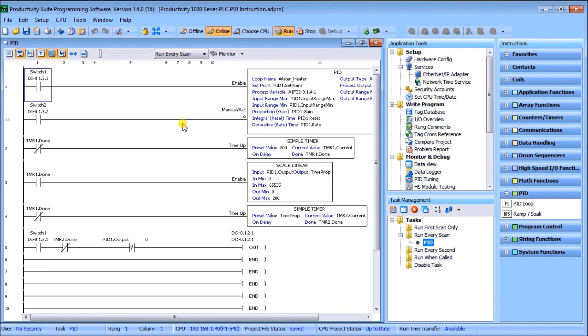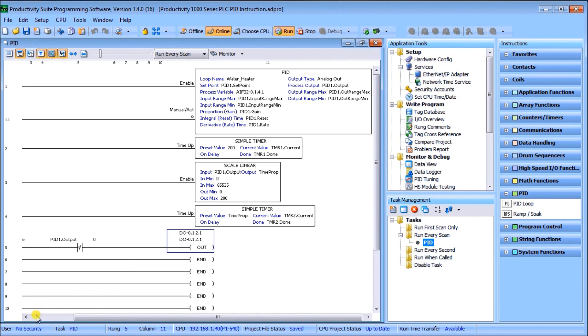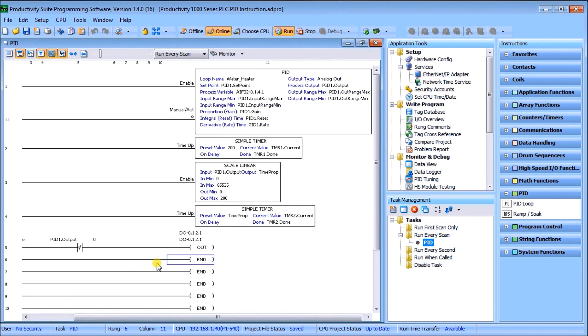Once we have our card set up, then everything we're going to be doing is actually using the relay output from our PLC, which is located right here. That relay output will be oscillating on and off based on the output of our PID. So this is going to be time proportional control for that relay.